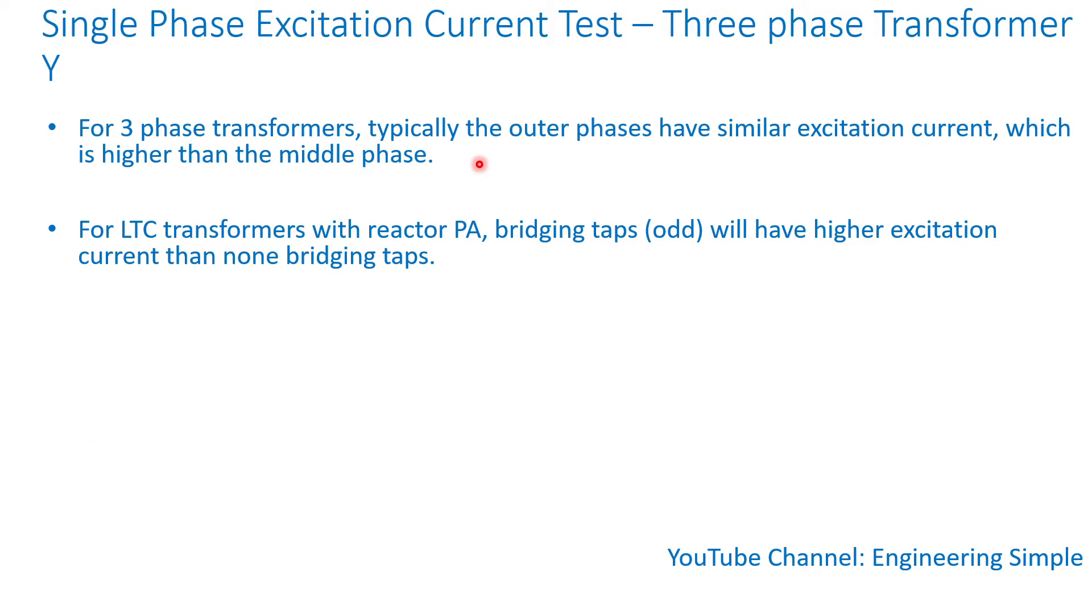For transformers with LTC or load tap changer with a reactor or preventive autotransformer, bridging taps, basically taps with numbers one, three, five, seven, nine, and so forth, will have higher excitation current than non-bridging taps.